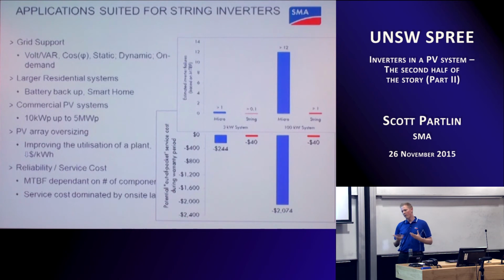And then there are the cost considerations of that. So obviously when a system fails, someone has to go on site, someone has to repair it. If it's a PV module, someone has to get up on the roof and replace that. If it's an isolator, someone has to go and replace that. If it's a microinverter, they have to get on the roof, they have to find it, they have to replace it. If it's a string inverter, it's on the ground. So these are some of the considerations that feed into that reliability or risk, that once you get over a certain size, favour a string inverter solution as opposed to a microinverter solution.